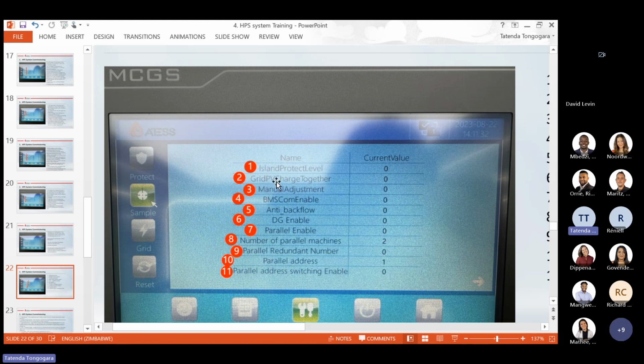And then we have grid and PV charge together. You need to enable this one for grid and PV to charge at the same time. And then on number 4, we have BMS communication enable. So if you have a BMS, you have to set it to 1. If you connect your BMS cable on CAN B, you set it to 1, you enable it. If you are using lead acid, then you leave it at 0.